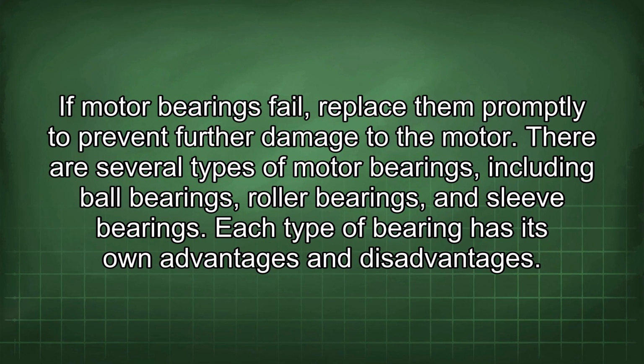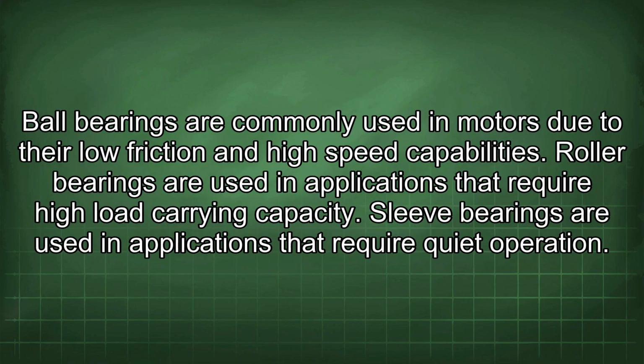There are several types of motor bearings, including ball bearings, roller bearings, and sleeve bearings. Each type of bearing has its own advantages and disadvantages. Ball bearings are commonly used in motors due to their low friction and high speed capabilities. Roller bearings are used in applications that require high load carrying capacity. Sleeve bearings are used in applications that require quiet operation.